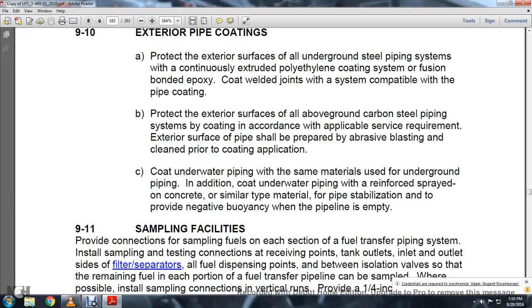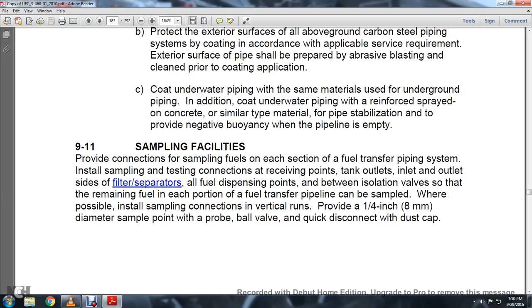9.11 Sampling facilities. Provide connections for sampling fuels on each section of the fuel transfer piping system. Install sample testing connections at the receiving point, tank outlets, and outlet side of filter separators, and at all fuel dispensing points between the isolation valves, so that the remaining fuel in each portion of the fuel transfer pipeline can be sampled. Where possible, install sample connections in vertical runs, provided with a 1/4 inch diameter sample point with a probe, a ball valve, and a quick disconnect with a dust cap.